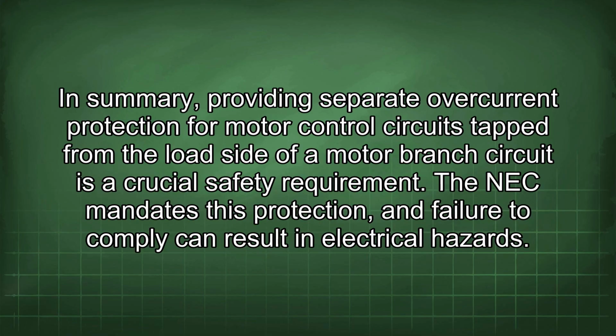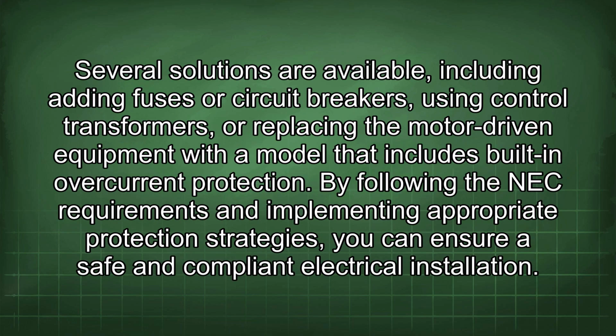In summary, providing separate overcurrent protection for motor control circuits tapped from the load side of a motor branch circuit is a crucial safety requirement. The NEC mandates this protection, and failure to comply can result in electrical hazards. Several solutions are available, including adding fuses or circuit breakers, using control transformers, or replacing the motor-driven equipment with a model that includes built-in overcurrent protection. By following the NEC requirements and implementing appropriate protection strategies, you can ensure a safe and compliant electrical installation.